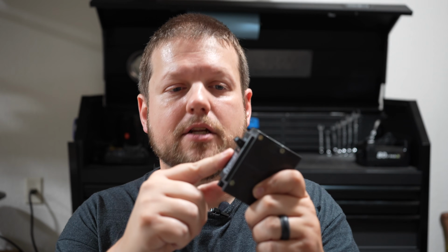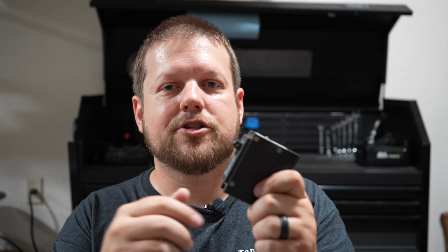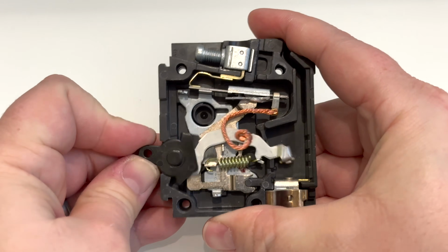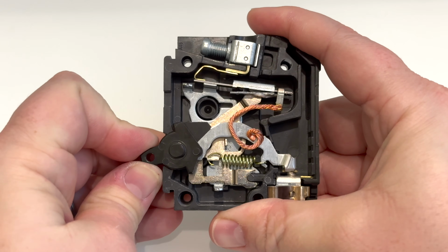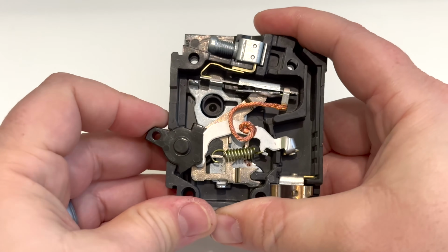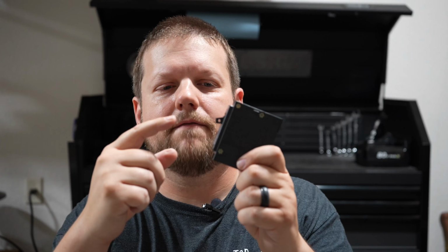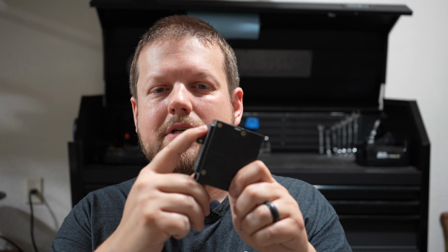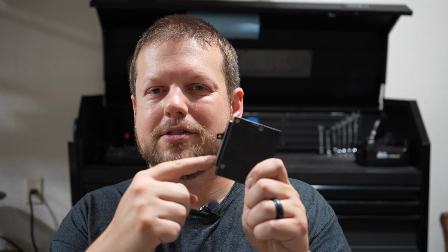So now when you're trying to reset one of these and it will not stay in the on position, if it doesn't click into place, then that's a better indication that there's something mechanically wrong inside of the breaker. Not always, but it is a good indication because there are mechanical components inside of this. These are designed to stay in an off state just in case. So if you can't get this to stay in the on position, it's a really good indication that there is something mechanically wrong inside. Now, if you can't reset one of these, it could simply just be doing its job.